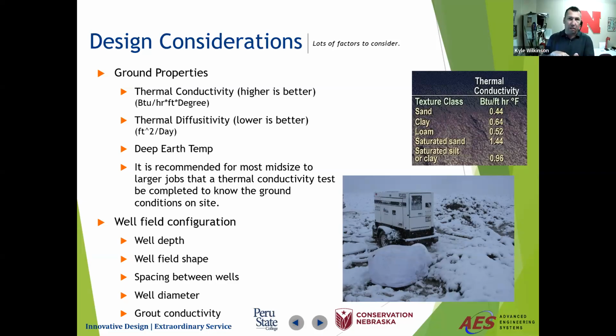Other things to consider is the depth of your wells. Sometimes, because you don't have much space, it's better to go deeper. Other times you want to keep it more spread out. If you have more of a heating dominated design, you might want to keep everything more tight together. If you have more of a cooling dominated design, you might want to spread it out more. So whether it's square, rectangular, and the spacing between the wells all plays into how well the energy is transferred. Typically, 20 feet is a common distance between the wells. And we said before, 6 inches is the well, and then you have your grout, and you have your roughly 3/4 to 1 1/4 inch pipe, depending on how much flow you're trying to move through it.